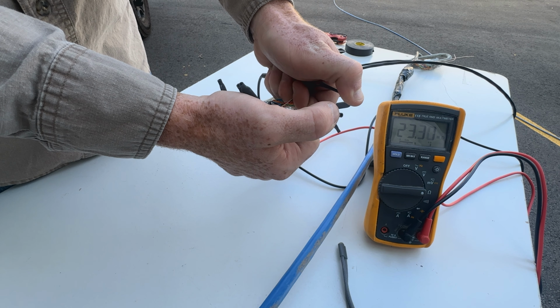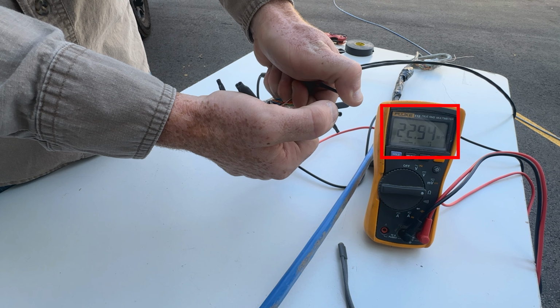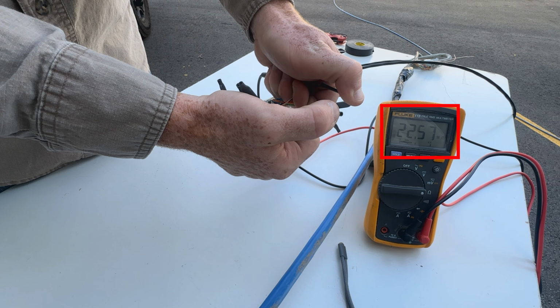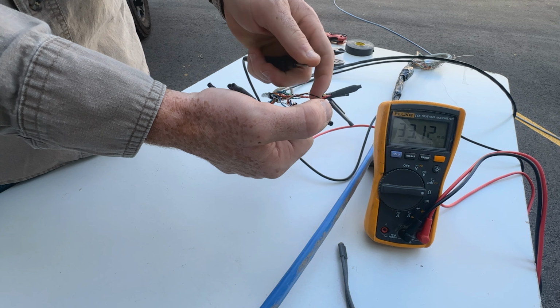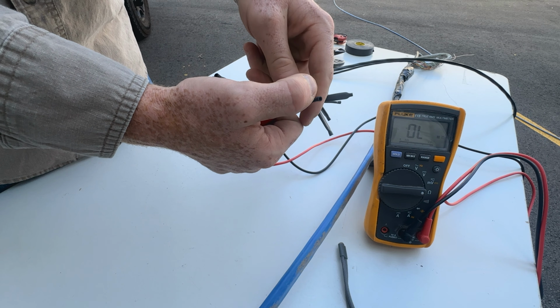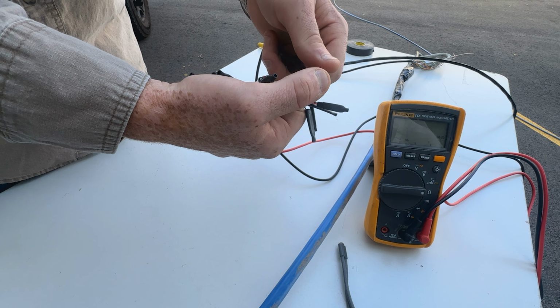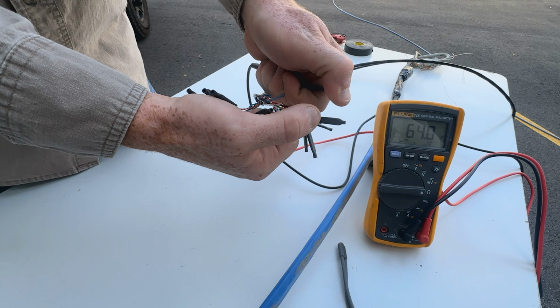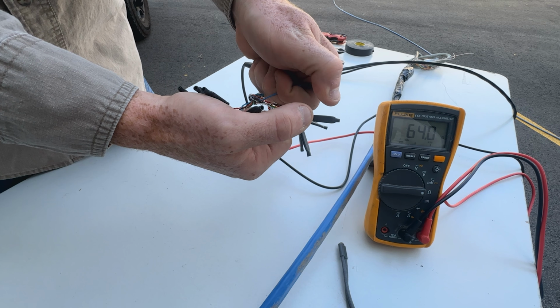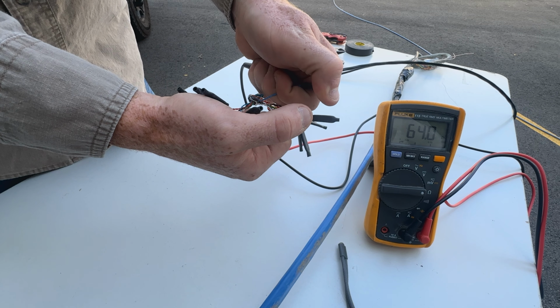If you look at our multimeter, the resistance is jumping around and cannot find a connection. This indicates that the thermocouple has been damaged. Now we can leave our one probe in the crimp with the 2 white wires and move the other probe into the crimp with the 2 blue wires, working our way up the cable. If you take a look at our multimeter now, you can see a solid number of 64. This indicates a thermocouple that is still intact.